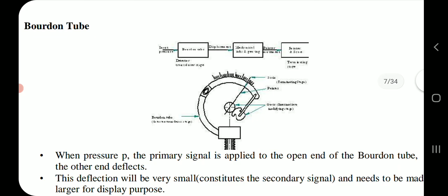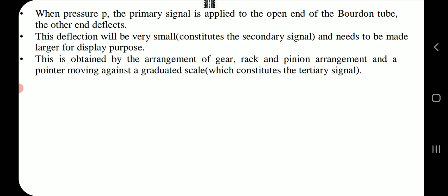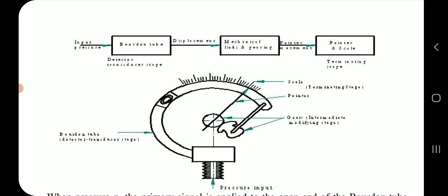Bourdon tube. When pressure P, the primary signal, is applied to the open end of the Bourdon tube, the other end deflects. This deflection will be very small, constitutes the secondary signal, and needs to be made larger for display purpose. This is obtained by a gear, rack and pinion arrangement and a pointer moving against a graduated scale, which constitutes the tertiary signal. Input pressure, Bourdon tube, displacement, mechanical links and gearing, pointer movement, pointer and scale, detector transducer stage, terminating stage.